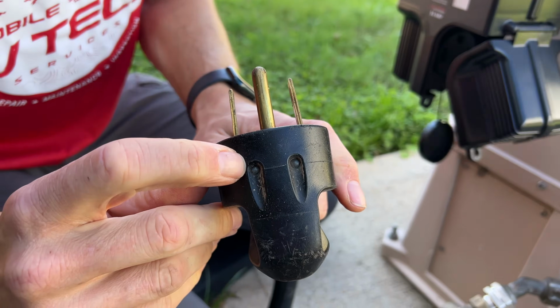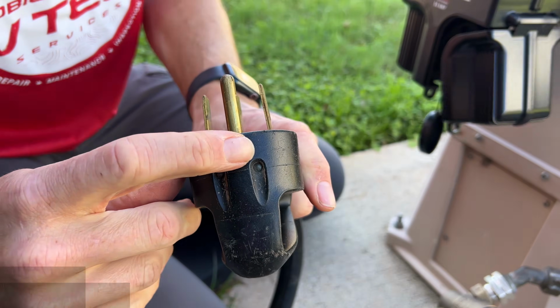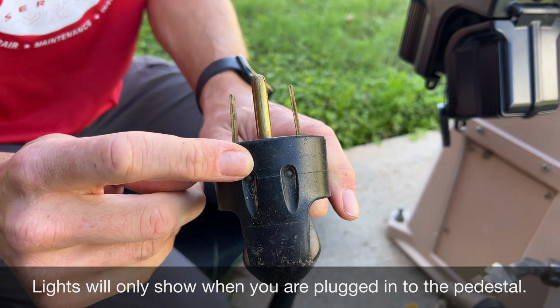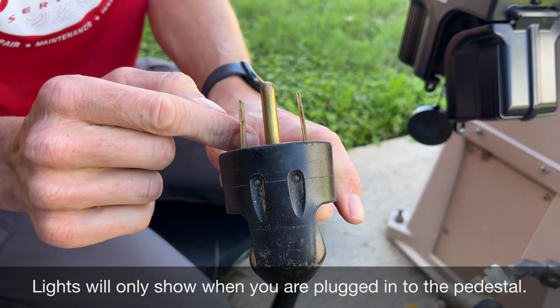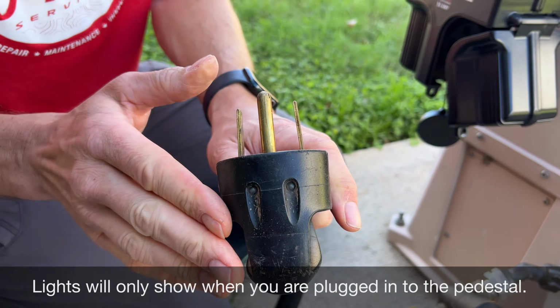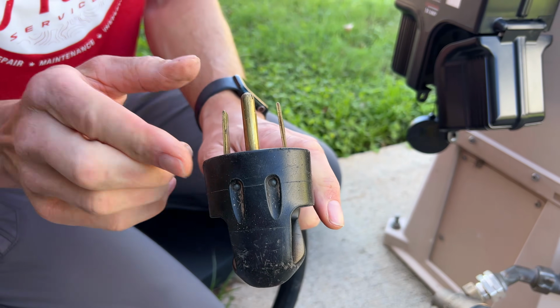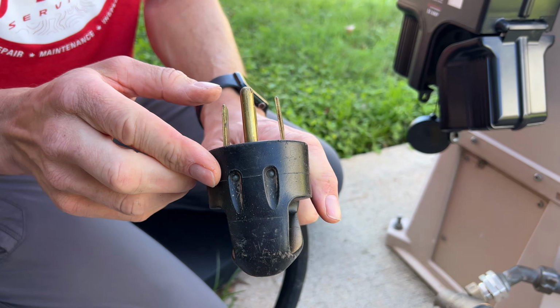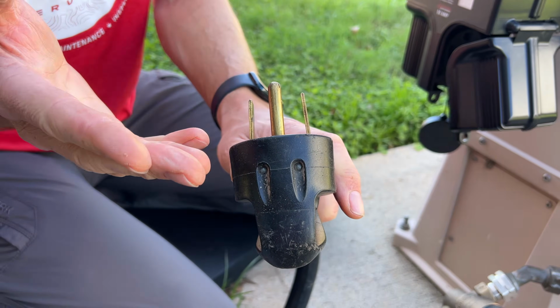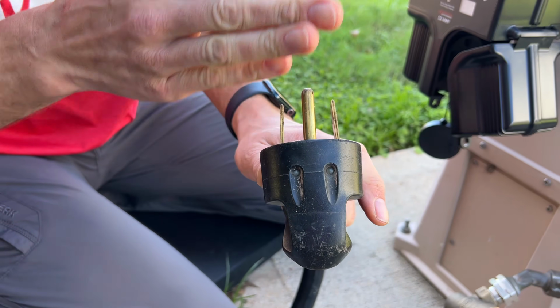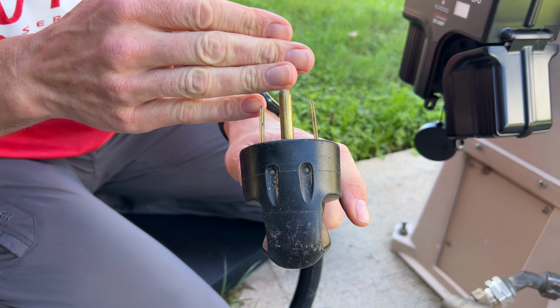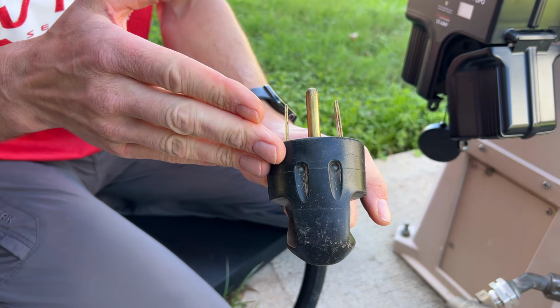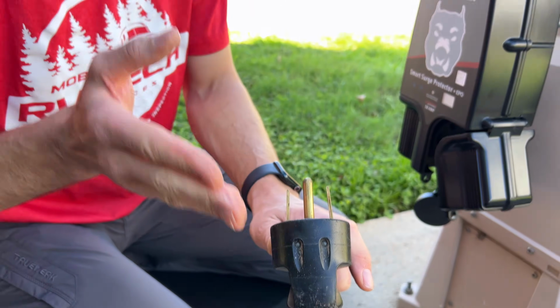Right here at the top are two LED lights. Those should both be on if we have 120 volts for each hot leg coming through. That's for your 50 amp outlet. Now, if only one of them is on, that could indicate there's a power issue for the pedestal, your cord, or somewhere in there. Now, I will say, sometimes the lights do just burn out. That's not a 100% indicator, but it's a place to start.